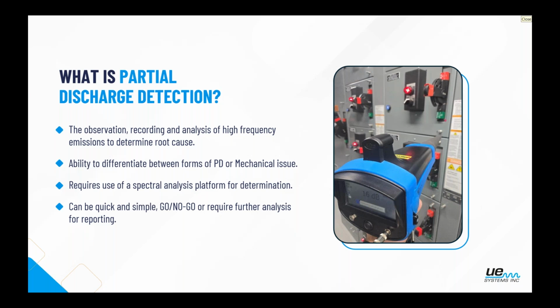So it's the sound emitted by these electrical events or anomalies. Now, once we actually take that sound and look at it and analyze it, we can determine if it is a form of partial discharge or if it might be a mechanical issue. So is it a tracking event happening inside this cabinet, or is it the nameplate vibrating on the door itself? Looking at the sound file, the signatures and the frequencies, we can determine between those.